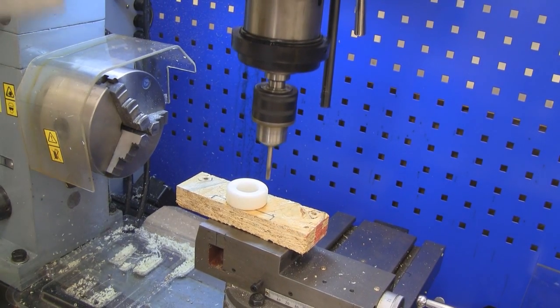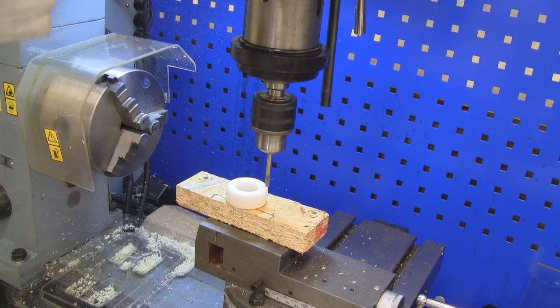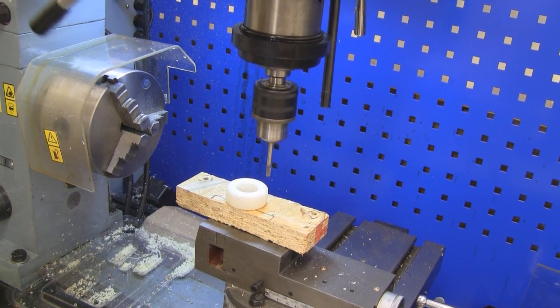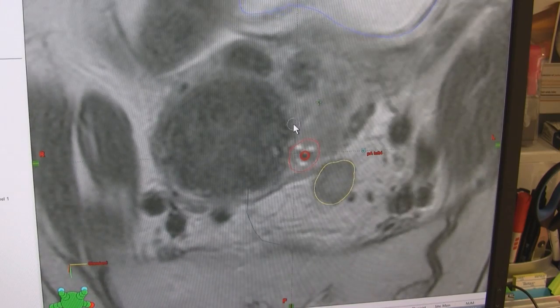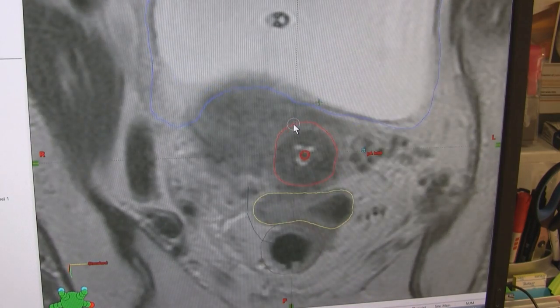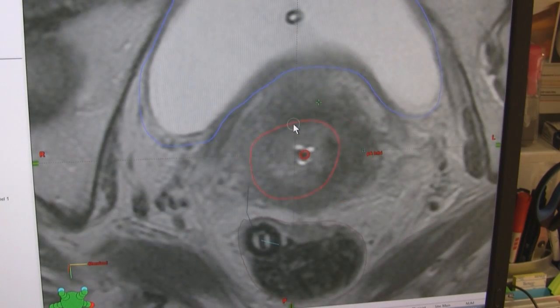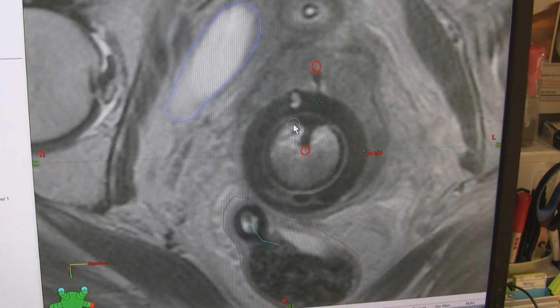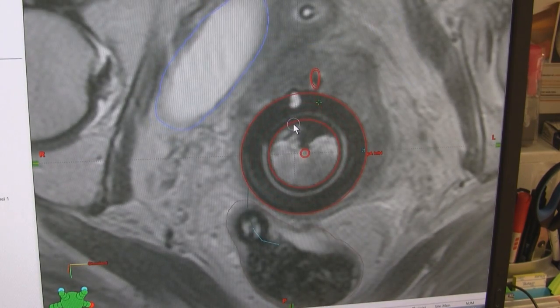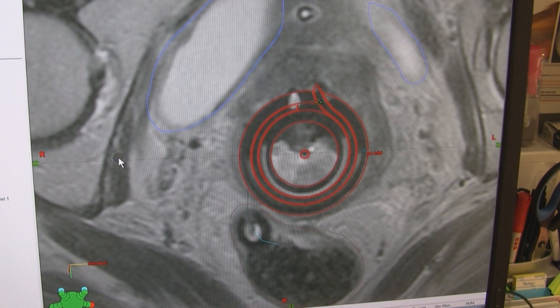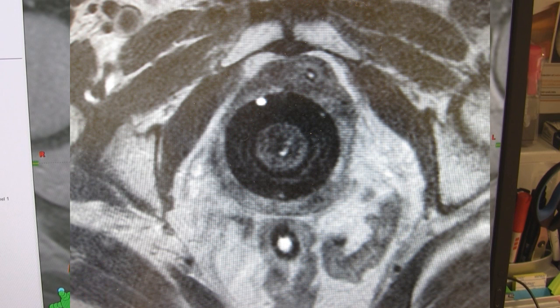To insert it into the ring build-up cap, by milling cutter we make a cylindrical groove perpendicular to the ring plane and parallel to the tandem tube, and as a result on the paraaxial MR images the 5 mm diameter tube with water should be seen as a good visible circle over an acceptable range of slices.